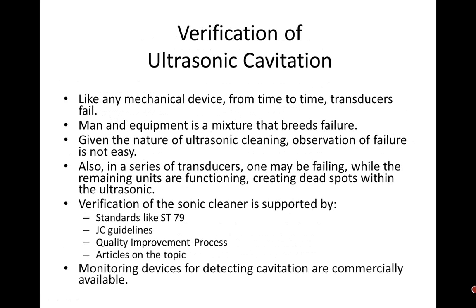What are you monitoring with, and what are you looking for? I still hear it at meetings, oh, the surveyor didn't ask me. They could ask you, and if you're following AAMI ST79, you should be checking minimum weekly, preferably daily, with something that gives feedback if it fails, so you can solve the issue. I've shared different articles on the topic, and there are enough articles supporting verifying your sonic cleaning activity. Monitoring devices for checking cavitation are commercially available and have been for quite a long time.